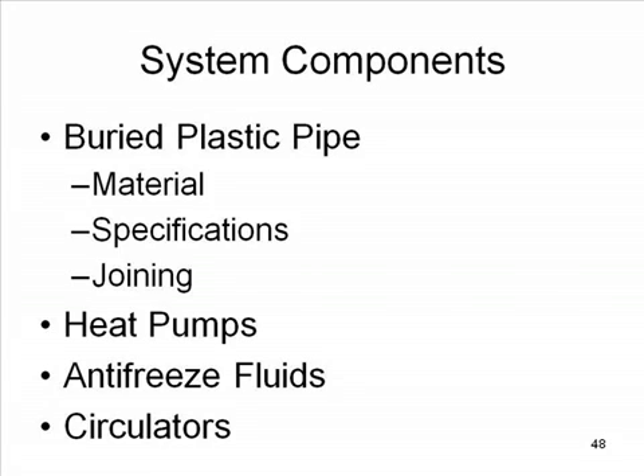Antifreeze fluids, if needed. We want something that's safe, non-toxic, non-corrosive, that will last a long time. And then circulators. I showed in the previous slide a primary and secondary pumping system. That's not the only one out there. We have a large number of projects where, like on that hybrid system there, each heat pump had its own circulator. That really minimizes the pumping costs. If you can design a heat exchanger system as well as the interior piping system that you can flush the air out of, there's no reason for you not trying something like that. But there are some design guidelines that are available for that.